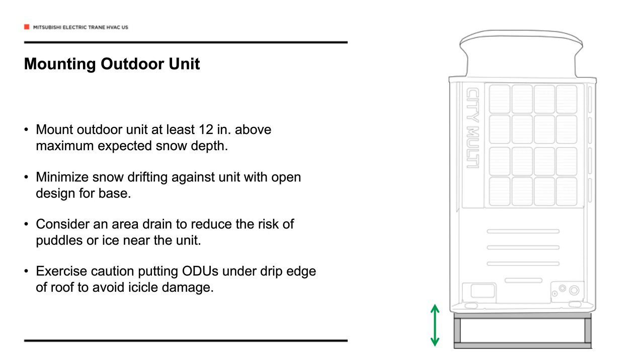You also want to give some consideration to what happens when this unit goes into defrost and that water basically sheds down the outside of the unit, where that water goes. So you want to make sure it's not a nearby sidewalk that is hindering egress into the building. You don't want people slipping and falling on the sidewalk because the condensate water sheds off the unit and then refreezes on the sidewalk. So just some things to think about.